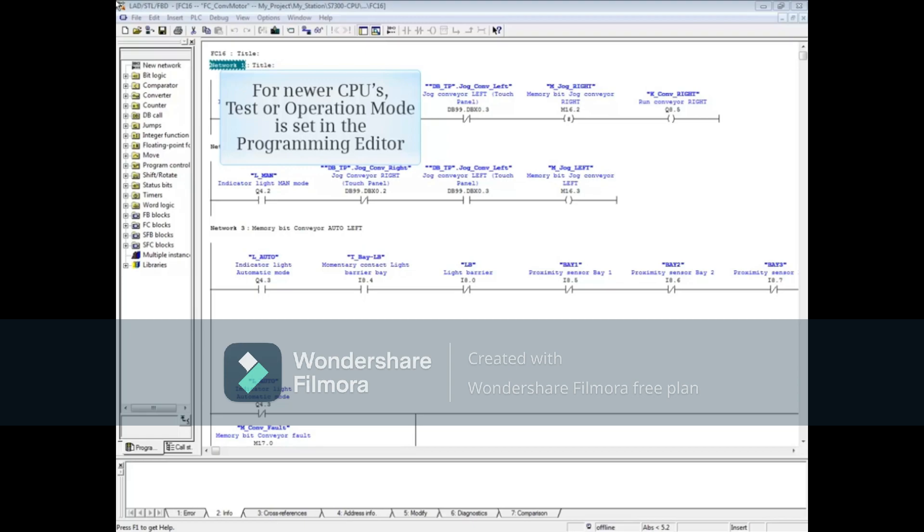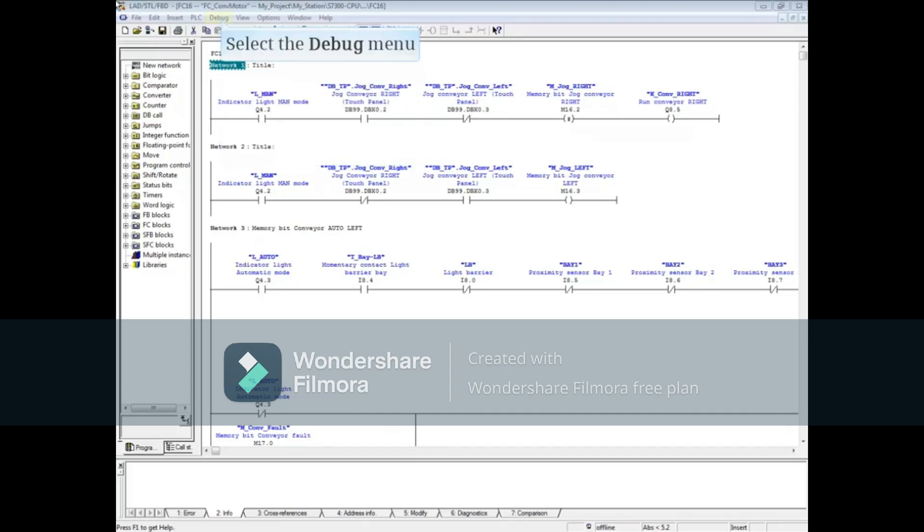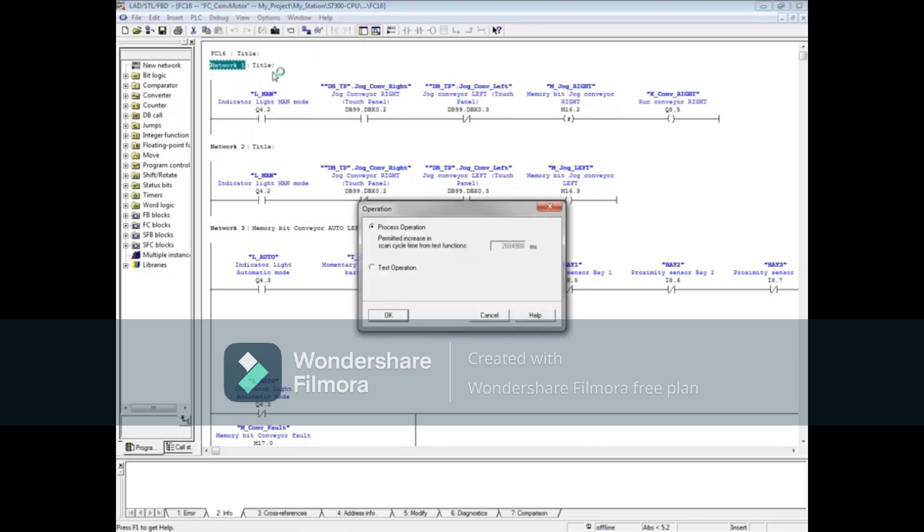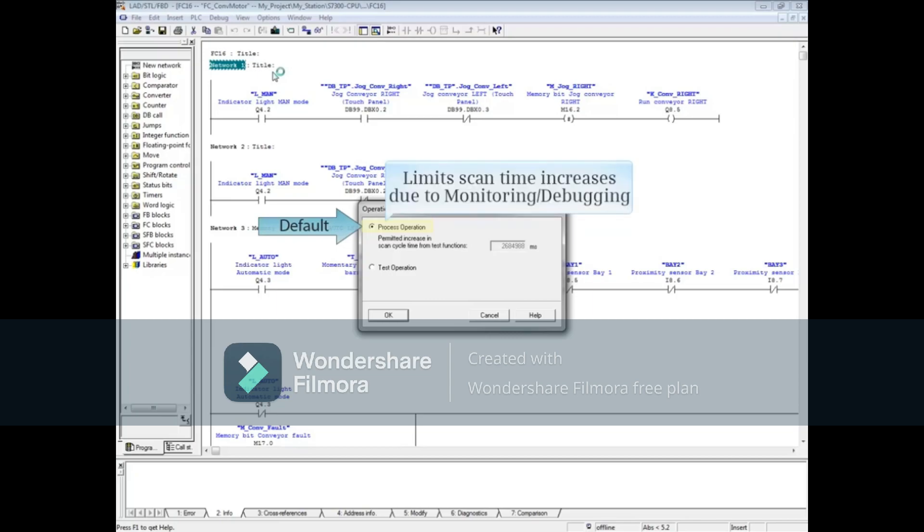For newer CPUs, the test or operation mode is set from the programming editor. To begin, select the Debug menu and choose Operation. The default is Process Operation, which limits the amount that scan time can be increased by monitoring.